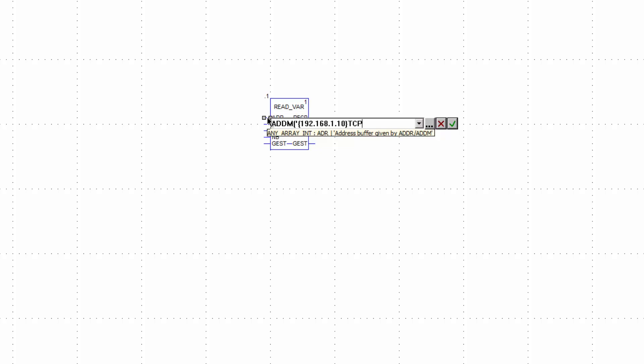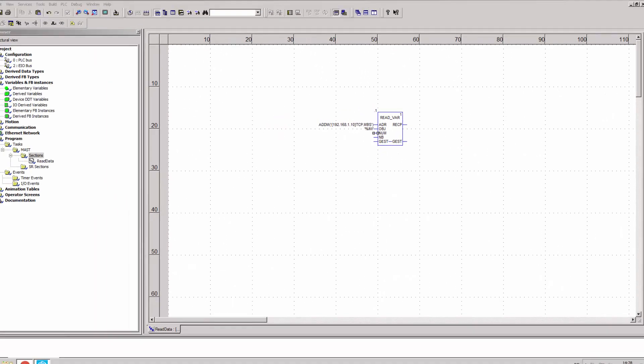The object type determines the Modbus address area of the register. For input registers, this is according to the IEC standard %IW. In the NUM parameter, the initial register must be entered from which you want to read. You can find this in the HTML report — in this case, it is 8663.